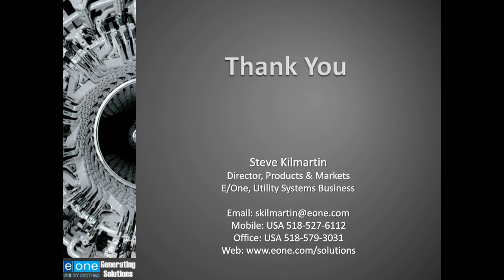Thank you very much. We're going to try to get to just a couple more before we end today. So this one is, what kind of maintenance is required on these systems, and how frequently does that maintenance need to be carried out? That varies on both pieces of equipment. The GCMX is very much what we refer to as a fit-and-forget piece of equipment. It gets installed, and if the generator is a baseload generator, it will not need to be adjusted or looked at. Now, I always recommend that the piece of equipment be looked at on a per-shift basis. So an operator will walk by, verify that the flow is correct, and verify that the output is correct. However, this isn't necessary. I only recommend it so that they're paying attention to it.